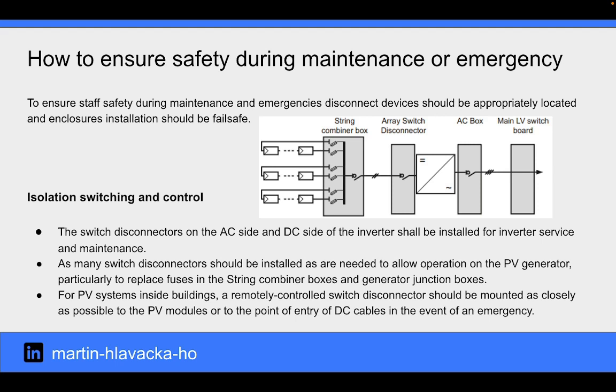To ensure staff safety during maintenance and emergencies, disconnect devices should be appropriately located and enclosures installation should be fail-safe. The switch disconnectors on the AC side and DC side of the inverter shall be installed for inverter service and maintenance. As many switch disconnectors should be installed as are needed to allow operation on the PV generator, particularly to replace fuses in the string combiner boxes and generator junction boxes. For PV systems inside buildings, a remotely controlled switch disconnector should be mounted as closely as possible to the PV modules or to the point of entry of DC cables in the event of an emergency.